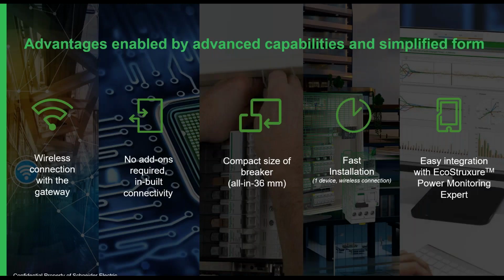So then that unlocks some significant advantages that are enabled by this digitization of a device. We've got wireless connection with the gateway. We've got no add-ons that are required. All the connectivity is really integrated and built into this single device. It's a compact size of breaker. It does all of those functions in 36mm. It's fast installation because it's only one device and it's not 5 individual pieces that you connect together with wires and then put it out onto a network. It's got easy integration into EcoStruxure Power Monitoring Expert.